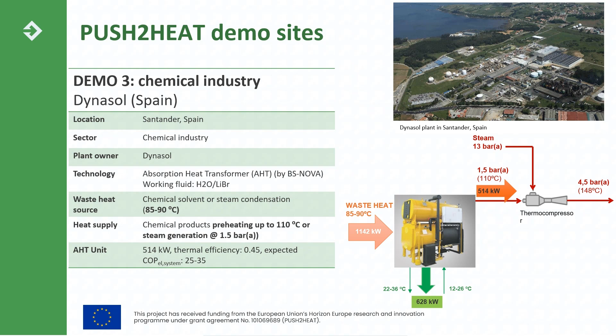Or it can be used to generate steam and introduce it in the process. That's the idea. Just to note, this is a different heat pump from the ones I mentioned for the other two demo sites. We are talking about a thermally driven heat pump, so it doesn't have a compressor, meaning we don't have such a high electricity consumption during operation. But we need to consume around 1 megawatt of waste heat to produce roughly half of that heat at a higher temperature level.